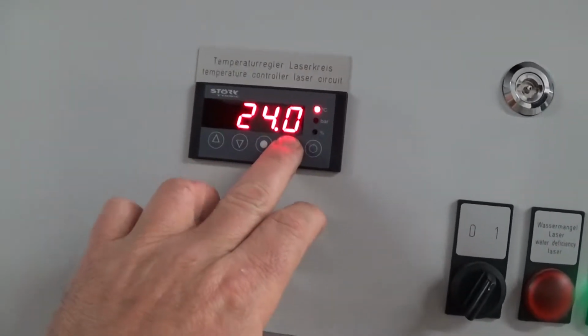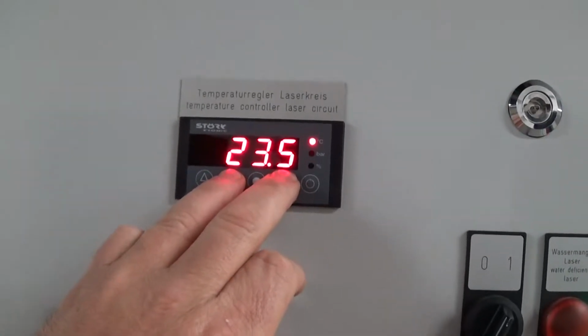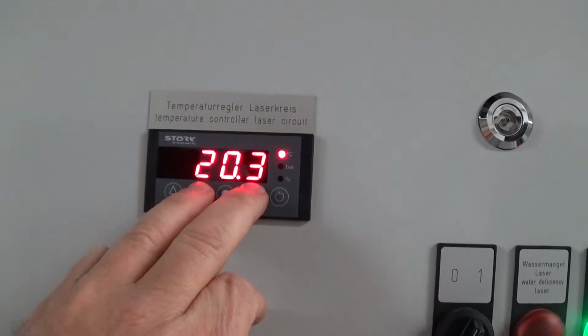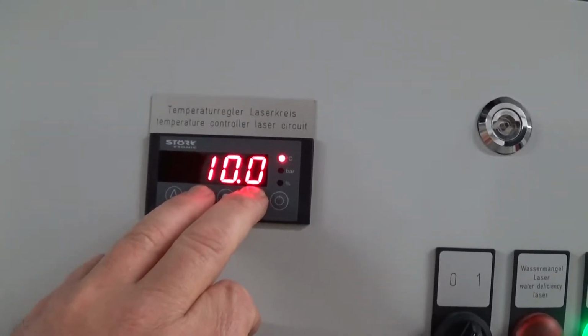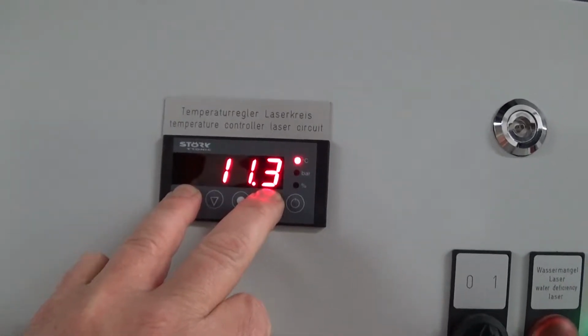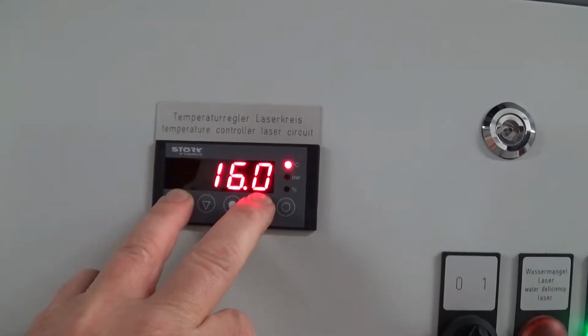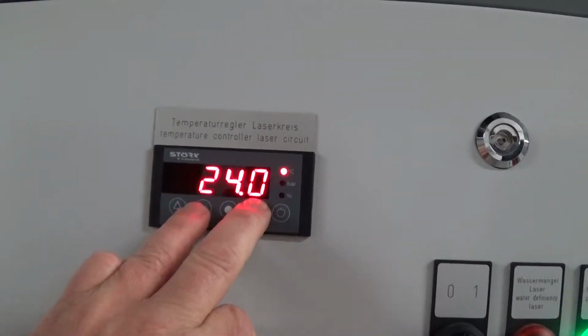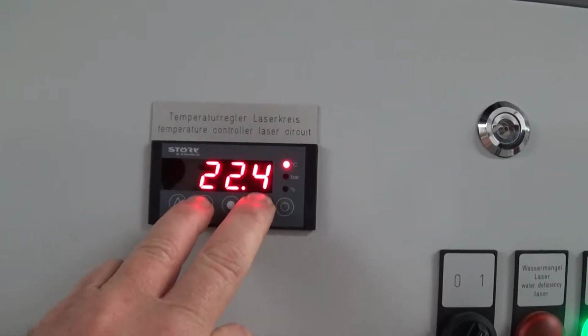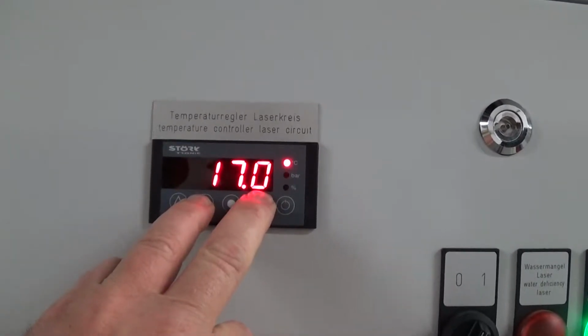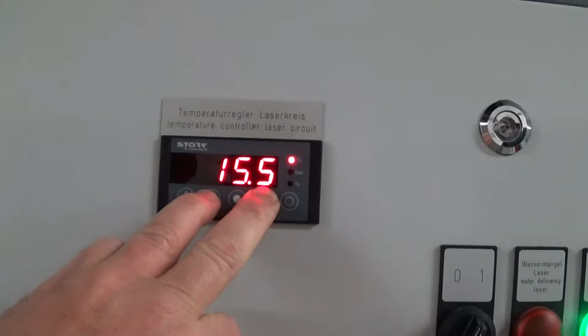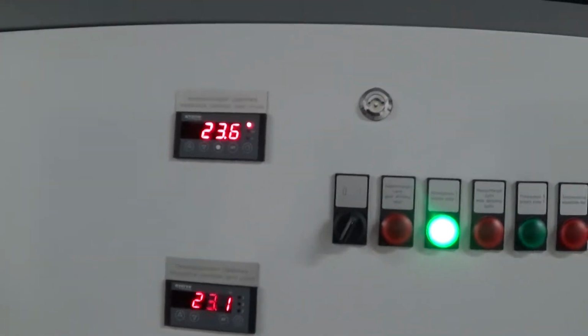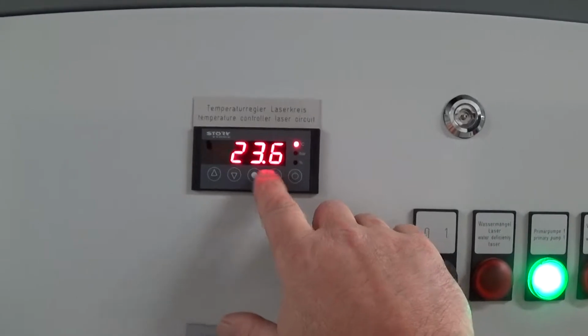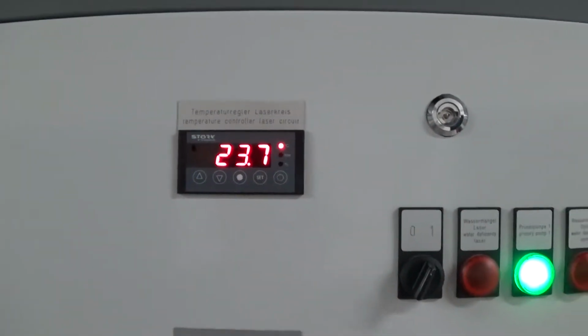And we have a set point range. You press set, and we can bring it down to, I think it's from 10 to 24, and obviously this is centigrade. So we're going to have a low of 10 and a high of 24. For this test for our customer, we're going to bring it down to 15 C, which is their desired cooling range for their manufacturing application. So there'll be a delay built into the control. Again, while you hold down the set, you press the up and down arrow key. Right now we do have it set at 15 centigrade, and it should start chilling after a time delay within the unit.